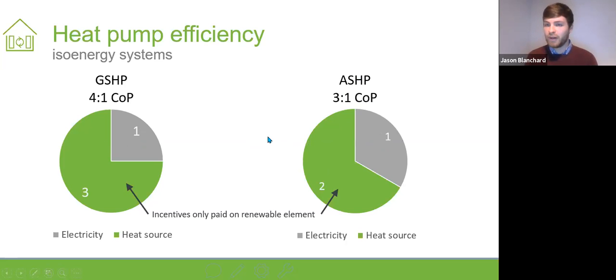These are very much rules of thumb, and an air source will vary its efficiency year round. Higher air temperature in the summer means air source will run far more efficiently. Equally, in summer you're not doing much heating for the home, so your air source is just focusing on hot water, which makes it more efficient too. So these things all play into the efficiency of a system, and whilst we can give rules of thumb for air source and ground source, it very much depends on the installation, the time of year, and what heating, hot water, and other services it's providing.